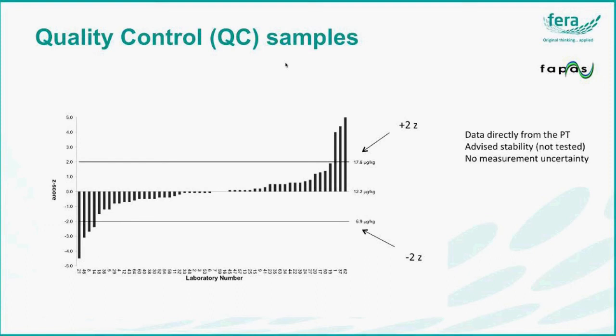For many of our products, we've made available the samples after the proficiency test for quality control purposes. It enables laboratories to troubleshoot performance or simply to use it as an ongoing mechanism for quality control outside of the formal PT process. The data for QCs are derived directly from the proficiency test. We advise on the stability, but the stability is not formally tested and we do not provide measurement uncertainty — it's just the PT data for that sample.